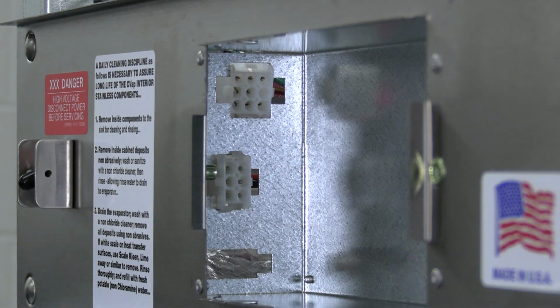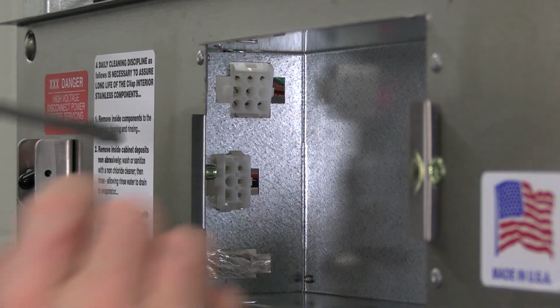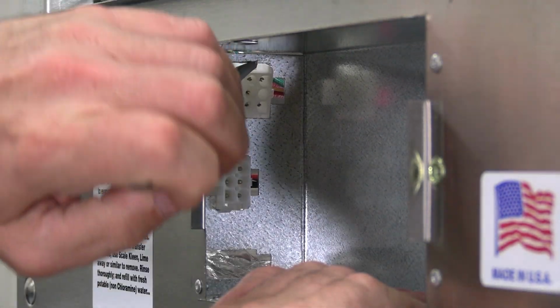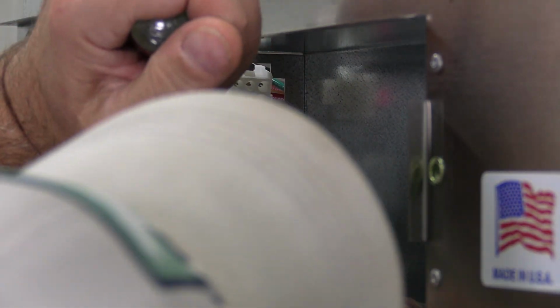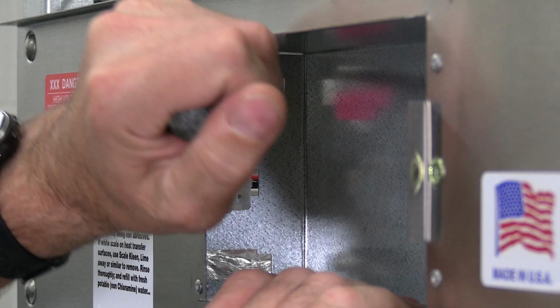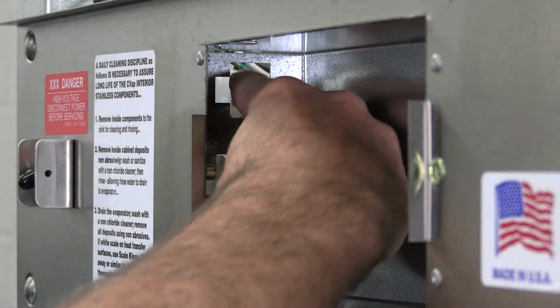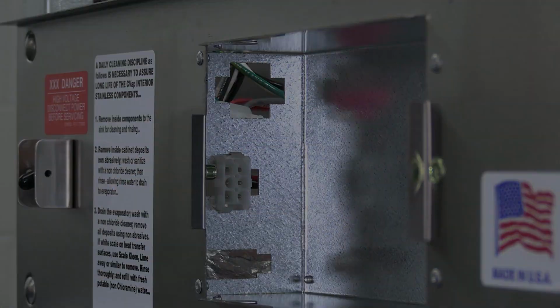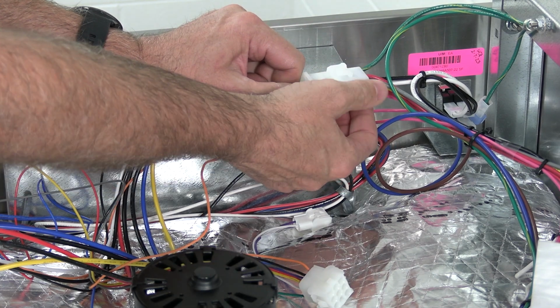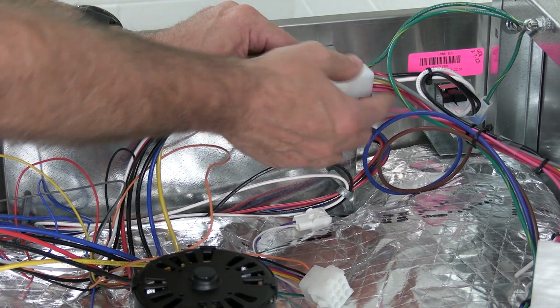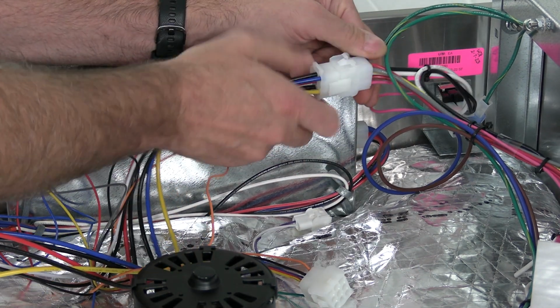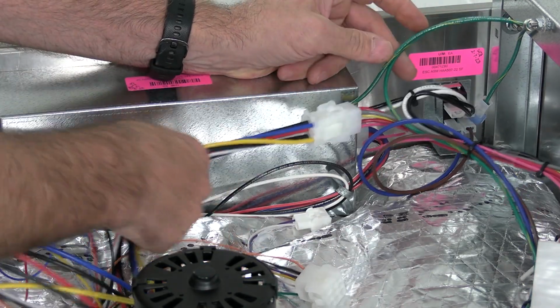Next, remove the control board. Using a flat-tip screwdriver, depress the tabs on the female 9-pin Molex connection in the cabinet housing and push the connection into the upper compartment. Locate the relay wire 9-pin. This will be the thicker wires, and connect to the female 9-pin that was just pushed into the upper cabinet.